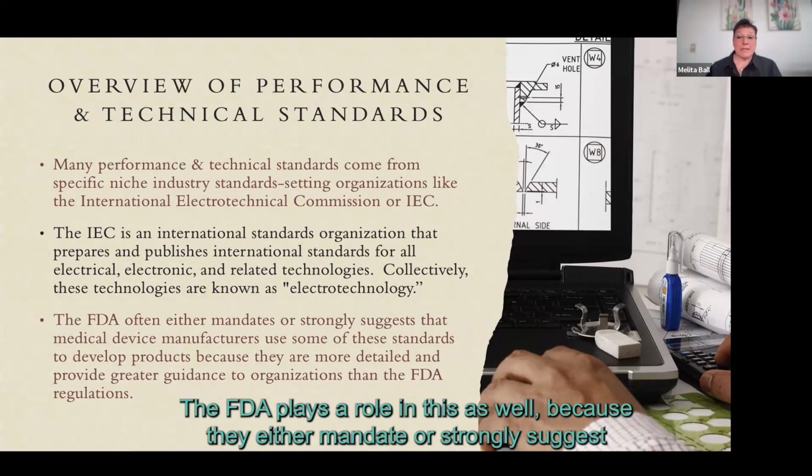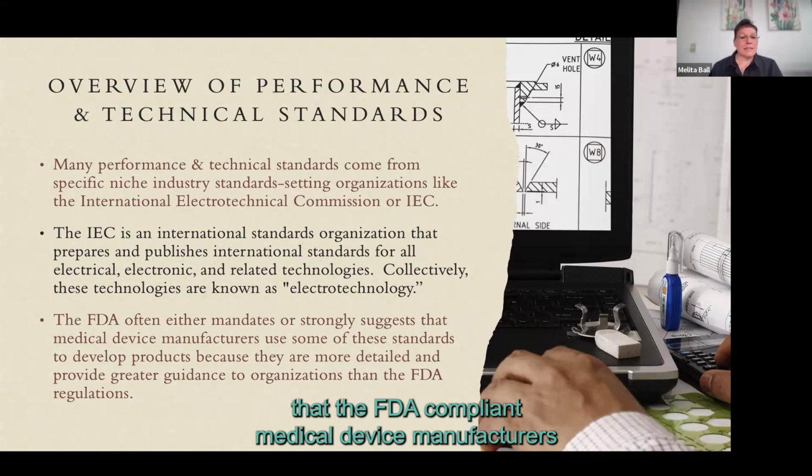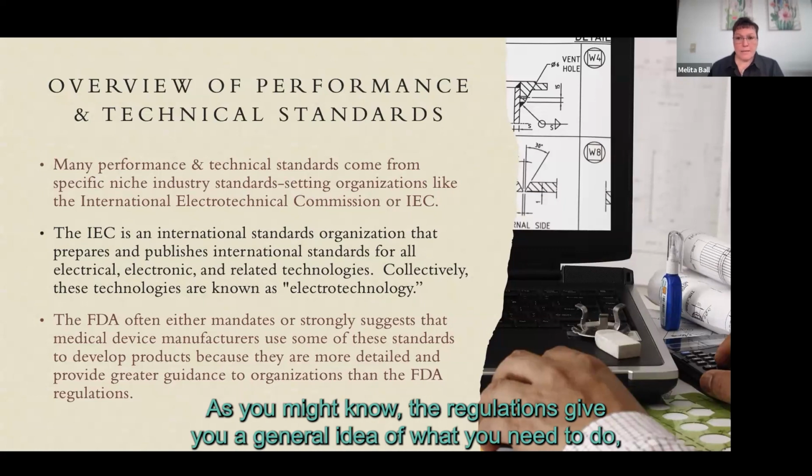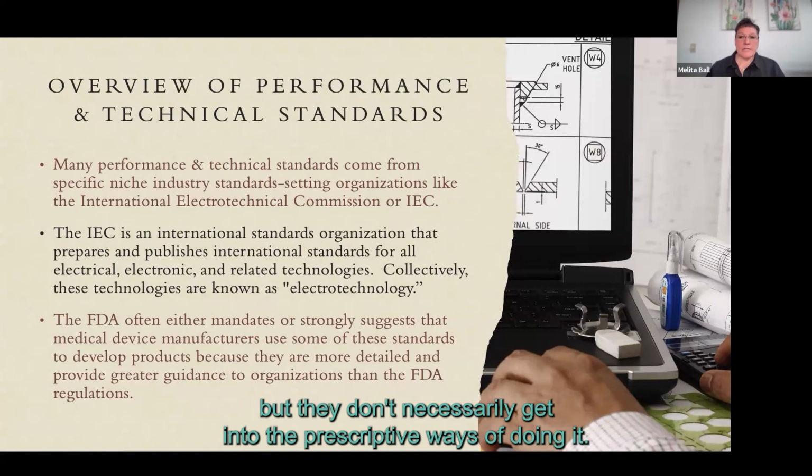The FDA plays a role in this as well, because they either mandate or strongly suggest that FDA compliant medical device manufacturers use some of these standards to develop products, because they're more detailed and provide greater guidance to the organizations than the FDA regulations themselves. As you might know, the regulations give you a general idea of what you need to do, but they don't necessarily get into the prescriptive ways of doing it.